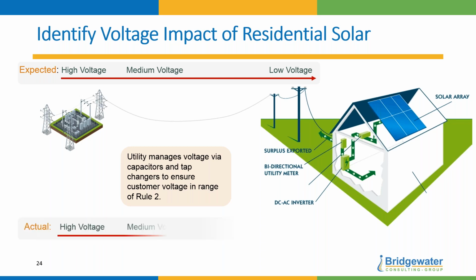Well, the game changer was that we started to see high voltage at the substation, medium voltage, and then very high voltage in some of these neighborhoods. The situation was that these residential solar inverters would kick up voltage, like pressure, having to increase voltage to push energy back into the system. So as penetration increased, the voltages became much higher.